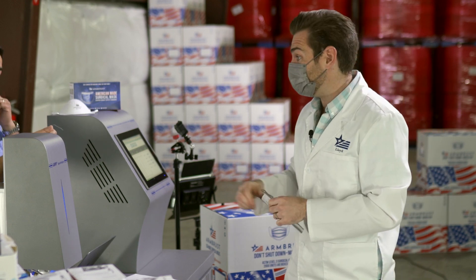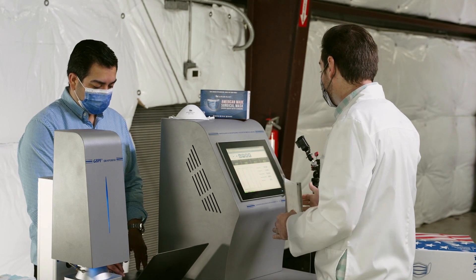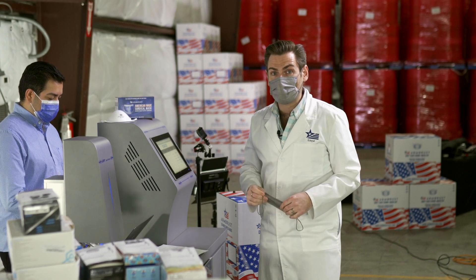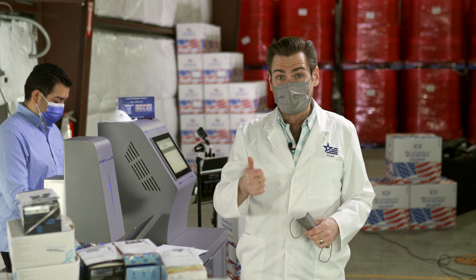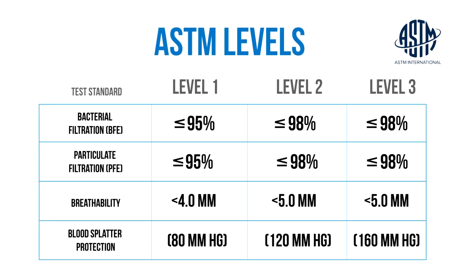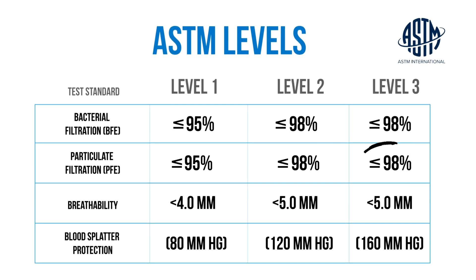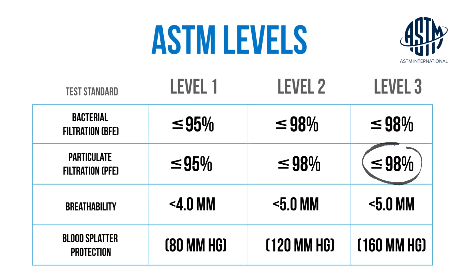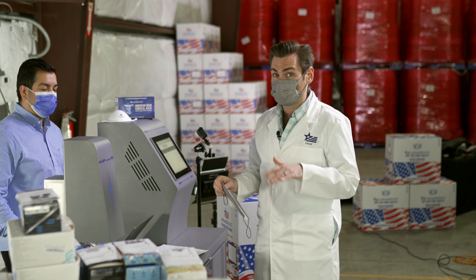The results are in and the filtration is 94.364%. That's lower than what we would call an ASTM level one, two, or three mask in the United States. My personal minimum is ASTM level three, which is 98% filtration — that's what our masks are made of. This one comes in at 94%, so it's actually below that.